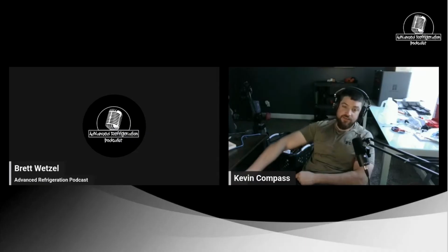They're considering the Visiograph a tool now. That's ridiculous. It is, because I think the Visiograph should be on every rack because it gives you a quick reference while you're watching other things. If you're watching the suction, you can see the flash tank and high pressure valve, what's going on in real time on the iPro instead of waiting for the comm to update. So it should be mandatory that it's on every rack. I don't understand why they wouldn't. To me, it's a safety thing not having it.